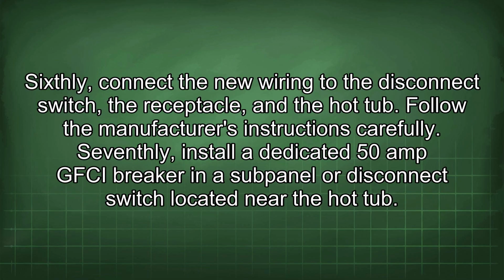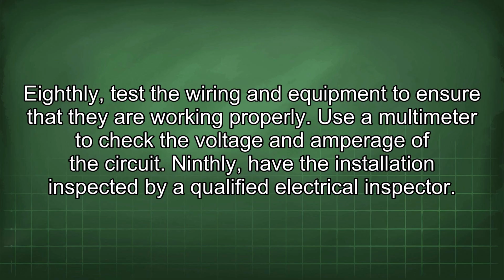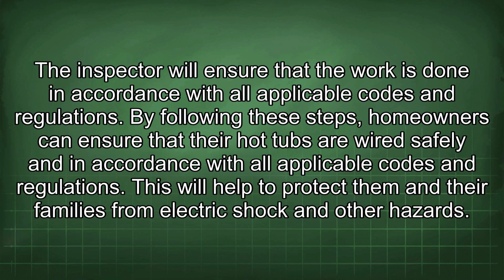Sixthly, connect the new wiring to the disconnect switch, the receptacle, and the hot tub. Follow the manufacturer's instructions carefully. Seventhly, install a dedicated 50 amp GFCI breaker in a subpanel or disconnect switch located near the hot tub. Eighthly, test the wiring and equipment to ensure that they are working properly. Use a multimeter to check the voltage and amperage of the circuit. Ninthly, have the installation inspected by a qualified electrical inspector. The inspector will ensure that the work is done in accordance with all applicable codes and regulations.